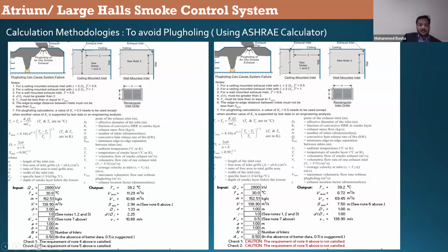It says check 1, check 2. The requirements of note above, 4 is satisfied, 5 is satisfied. What is 4 and 5? D by DI, where D, the small d, is the total height, and DI, which is given here, is the effective diameter of the inlet. It shall be greater than 2. And Vs must be less than or equal to Vmax. What is Vs? Volumetric flow rate of one exhaust inlet. That must be lesser than Vmax. If it is not, it will cause plug holing.